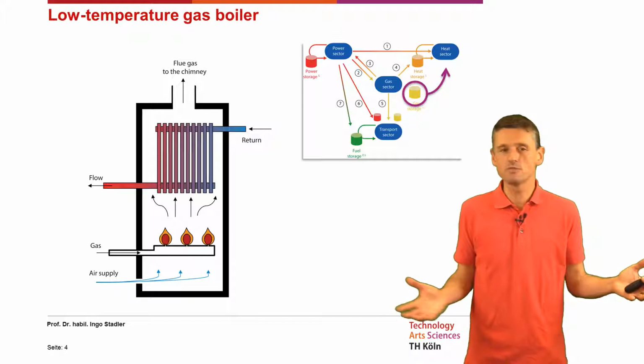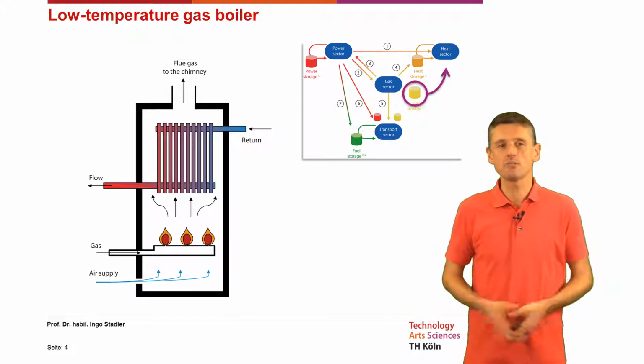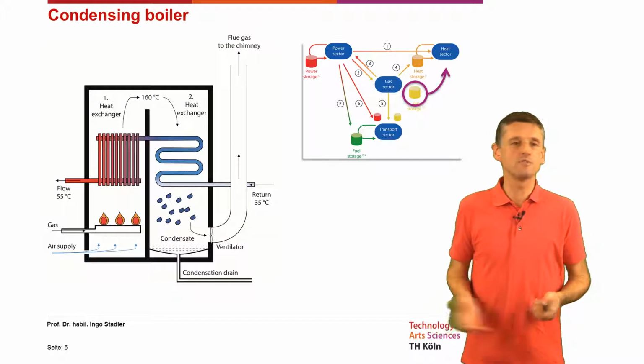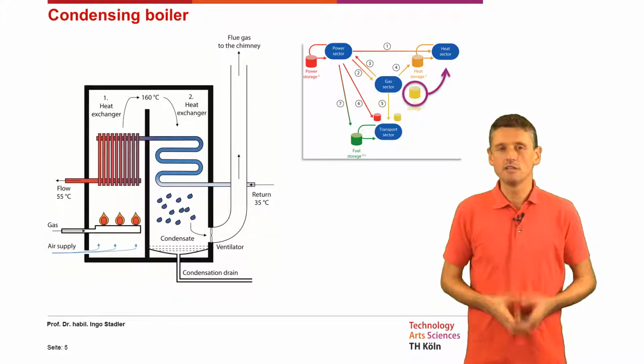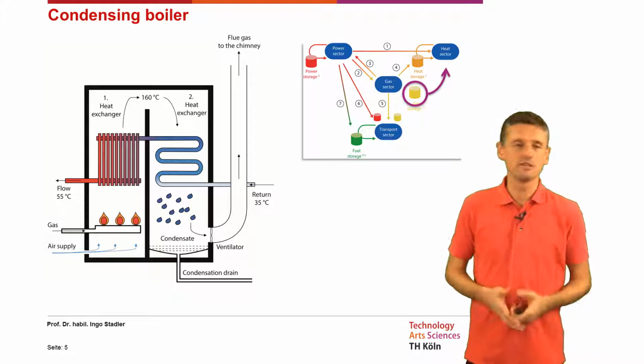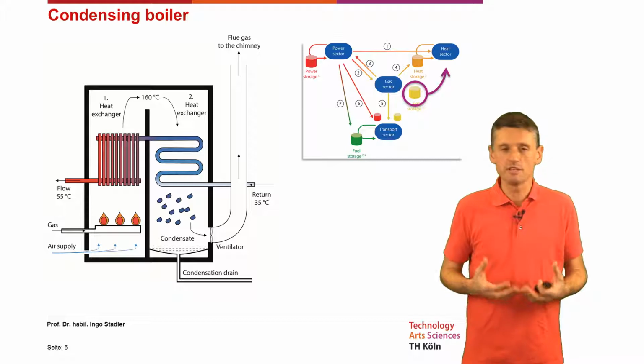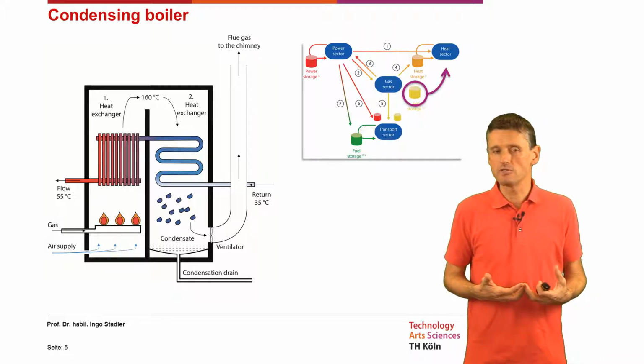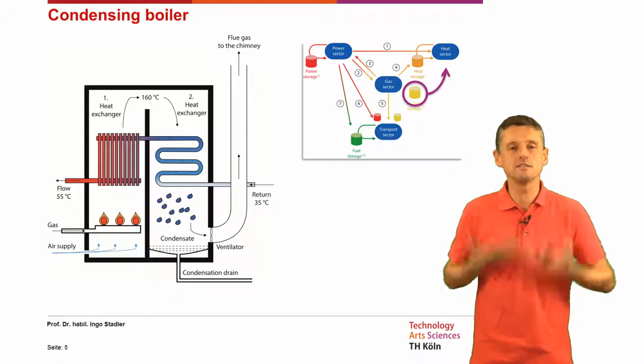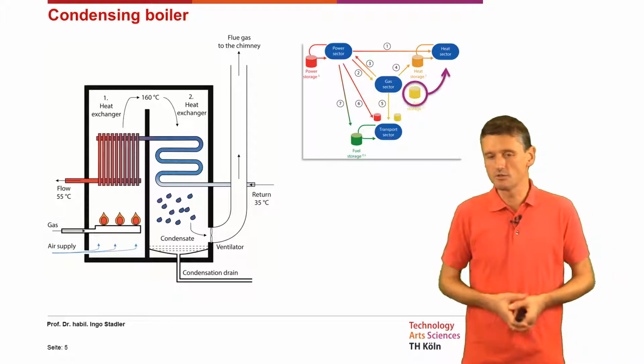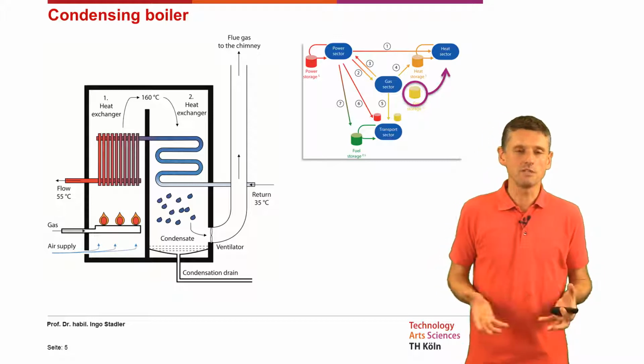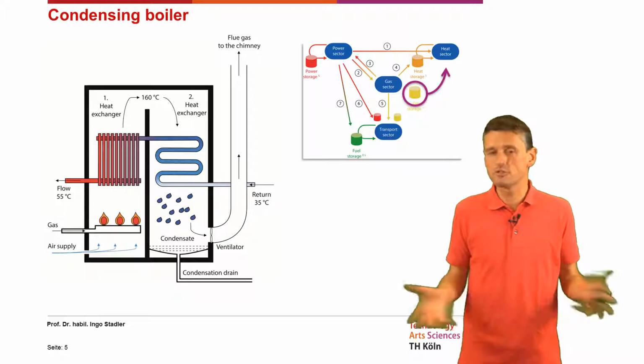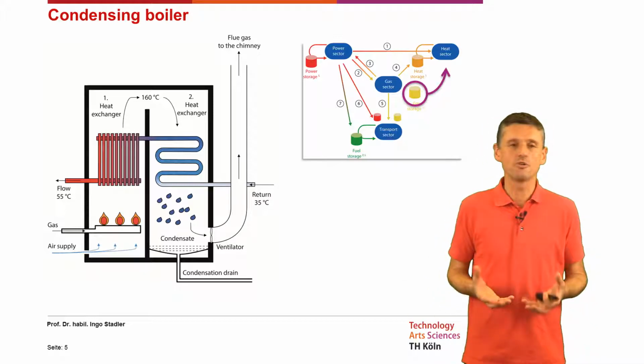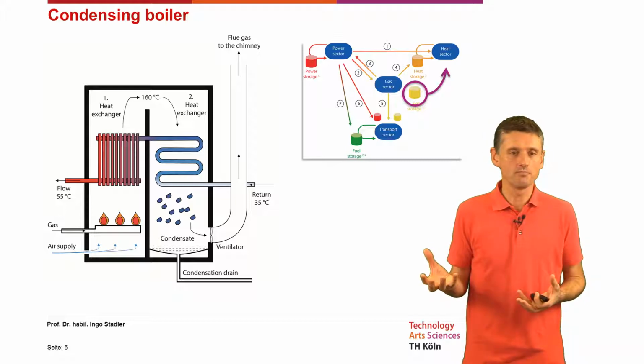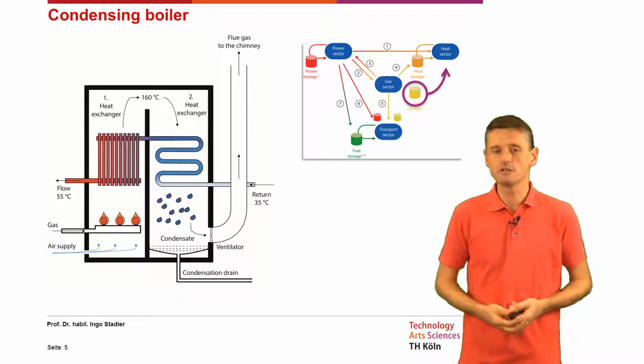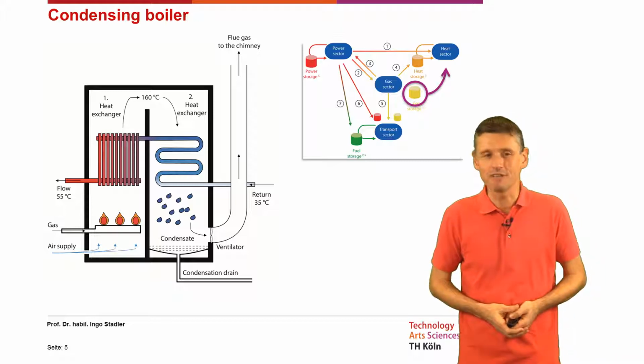Or we can use it completely in the heating sector, for example in a low temperature gas boiler, or a more advanced technology like a condensing boiler. Natural gas, as well as the renewably generated version, contains some water in steam form when burned, and there is a lot of energy contained. When you condense this water, we can increase the efficiency of those boilers - sometimes we see efficiency quoted as more than 100%. That's nonsense - it's only marketing, or a wrong physical constant being put in relation, but efficiency is never higher than 100%.